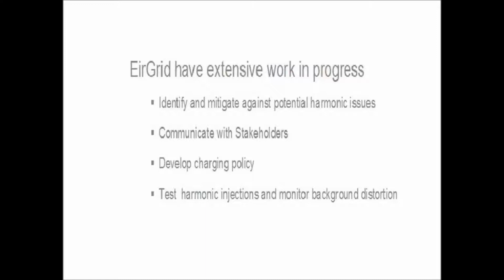And then obviously testing the harmonic injections and the background distortion, you just have to keep monitoring it all the time. And we're reviewing that grid code clause, because you can see that it covers it, but there are other things that can come under it, and because this area is evolving all the time, we need to make sure that the grid code is up to date, and that we can effectively police the system with it. And then internationally, the same sort of thing is going on. Other system operators are trying to test for all these harmonic injections in their systems, monitor them, and mitigate against them by putting in filters or increasing the system strength or whatever it happens to be.